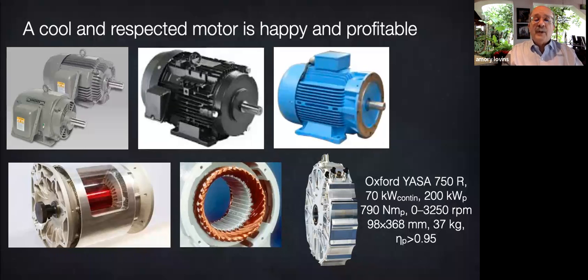Fanatically keeping even the tiniest trace of water out of the bearings. And just good housekeeping that keeps the motor clean, dry, cool, and quiet. Not in the sun, not next to a steam pipe, not smothered in dust or in multiple coats of paint so the heat can't escape. Procuring the motor starts with the actual measured load regime, and then it uses MotorMaster Plus software or its foreign equivalent to buy the very best motor for that job.